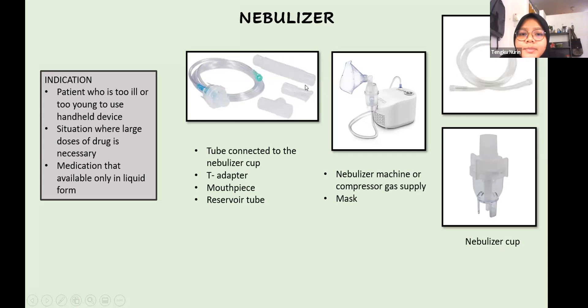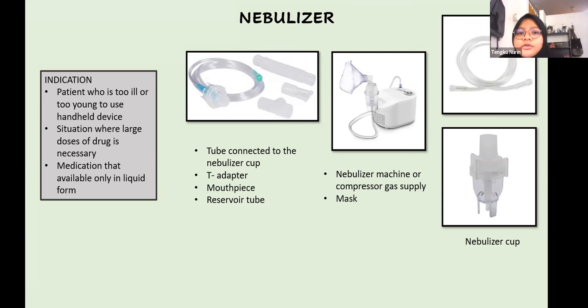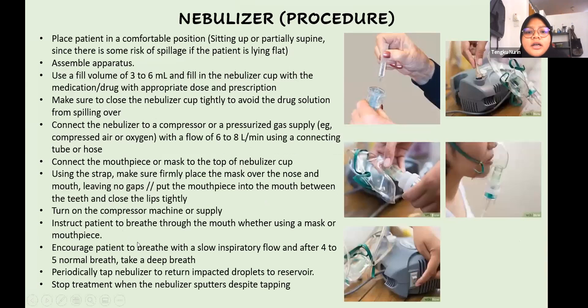The components of a nebulizer include: the compressor or pressurized gas supply, the connecting tube, the nebulizer cup for medication, and either a mouthpiece with T-adapter and reservoir tube, or a mask. The mouthpiece is more efficient for drug delivery — it has no leakage and no drug deposit on the face. The mask is easier for patients who cannot use the mouthpiece but is prone to leakage and less efficient, with drug potentially depositing on the face and nasal passages.